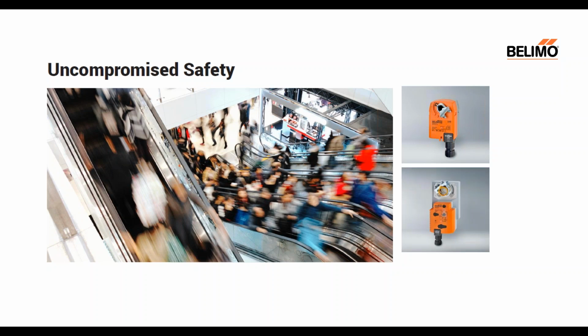The high-quality spring return and electronic fail-safe actuators provide reliable operation in case of a critical event. Quality assurance procedures ensure 100% inspection of each device, complete traceability, and 90 test routines to ensure that the highest quality standards are met. Belimo's patented SuperCap energy management algorithm safely charges and discharges the energy reliably for roughly 15 years or greater than 100,000 full cycles.